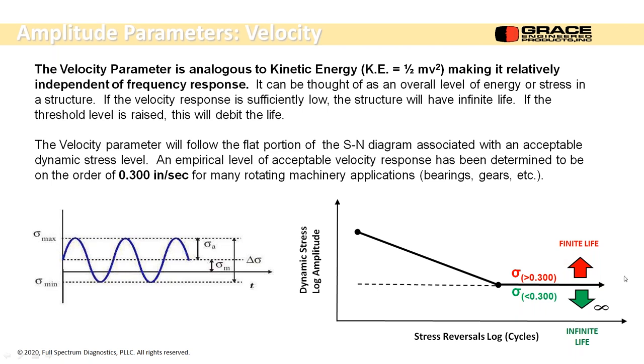Now, why is this important? This flat part of the curve is velocity. It's an energy level. It's not related to frequency, and it's flat. So if my frequency is 1800 RPM, I have to worry about 0.3 inches per second. If my frequency is 5400 RPM, same thing. I look at just a threshold level. Okay? It makes it so much simpler. So, you know, it's easy.